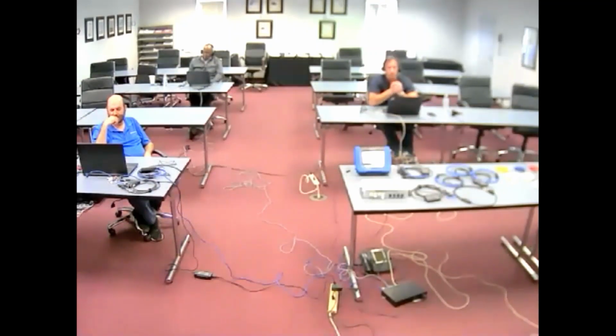There's really no normal reason to stop other than maybe memory filled, something it's programmed to do. But there can be exception situations where the battery or the instrument loses power, as you're alluding to, and the battery depletes. In those situations, it'll restore monitoring once it's back energized and gets mains power back.